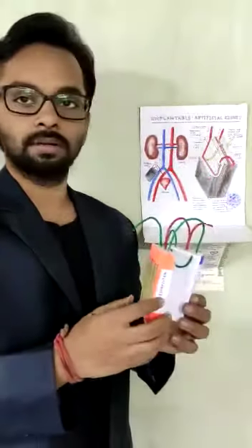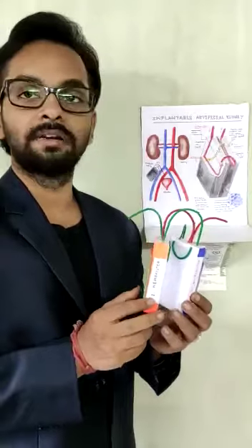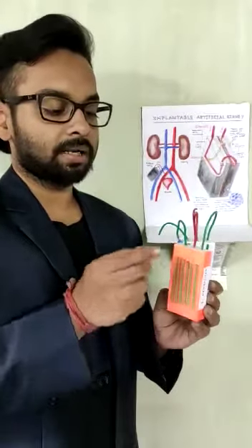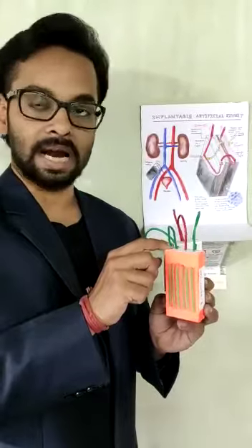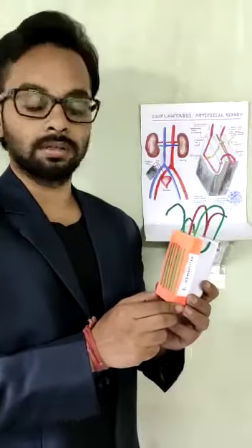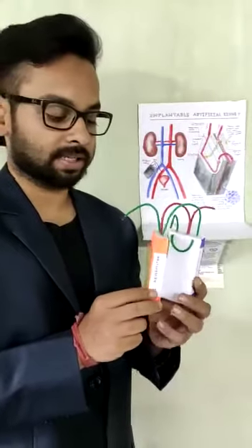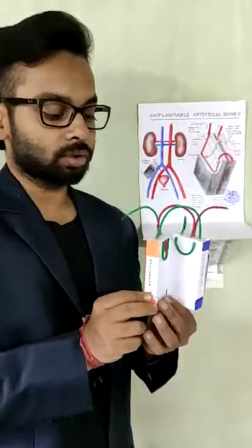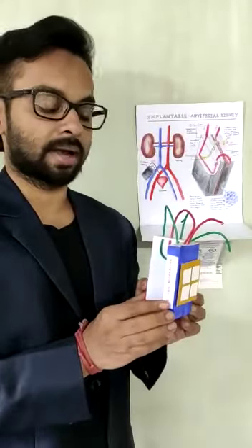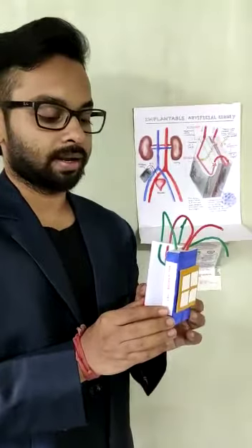This entire device consists of two chambers. The left chamber is essentially a haemofilter where filtration of the blood takes place. The blood enters from the patient's renal artery into this chamber, which consists of silicon membranes with microscopic pores or silicon tubules where the filtration takes place. In this chamber the blood is rid of excess water, toxins, glucose, salts, and other components.